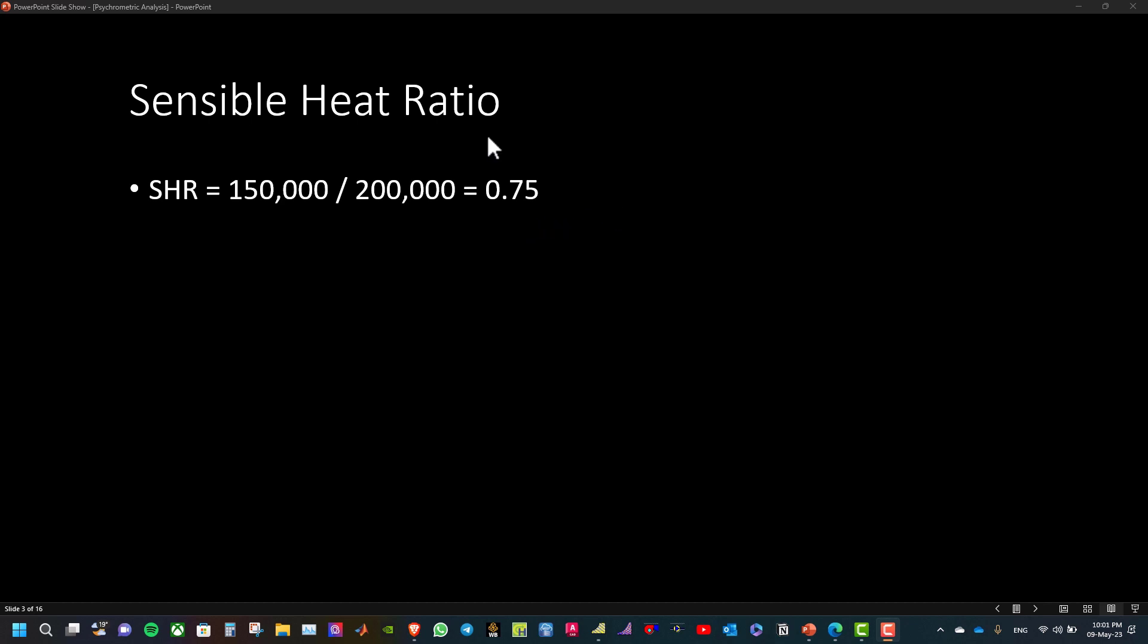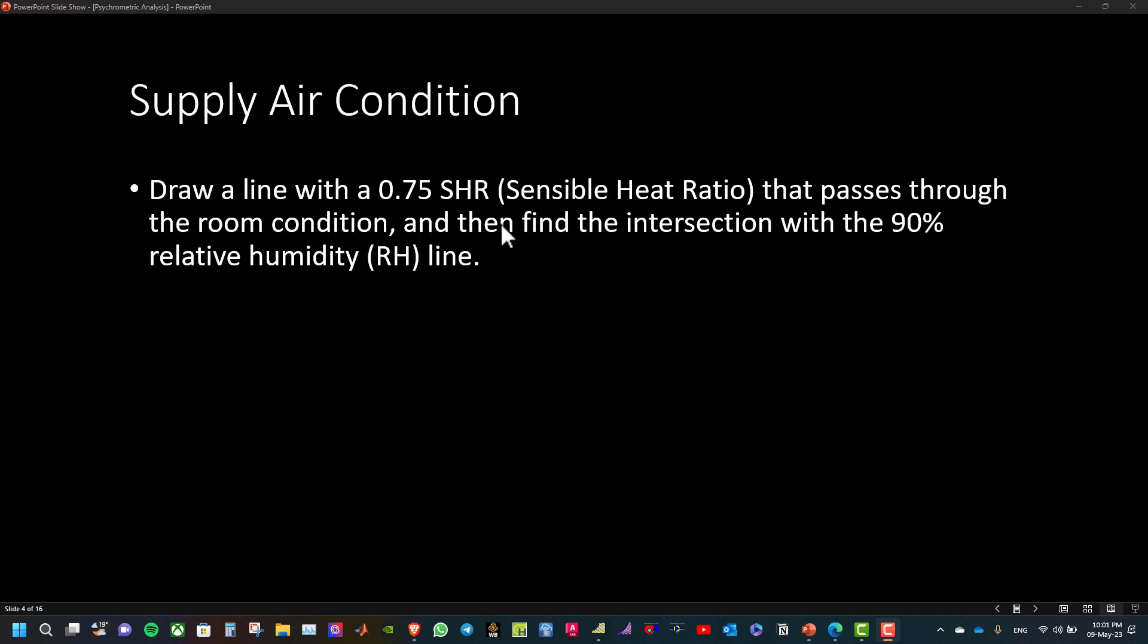Then, we will use the psychrometric analysis tool to find the supply air condition. How can we do that? Draw a line with a 0.75 sensible heat ratio that passes through the room condition and then find the intersection with the 90% relative humidity line.